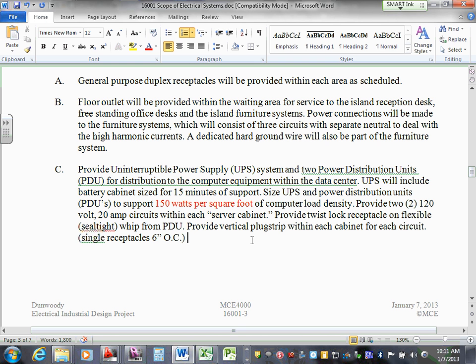Chad, in my notes I'm going to write a change so that instead of a 120 volt 20 amp circuit, I'm going to ask for a 208 volt 30 amp, probably a 3-phase whip from the A side and B side. Because if I don't bump up that whip requirement to the rack, there's no way we're going to consume all that power we have stored up in those UPS modules. I'll send you an email with the change, or you can just change it if you want.